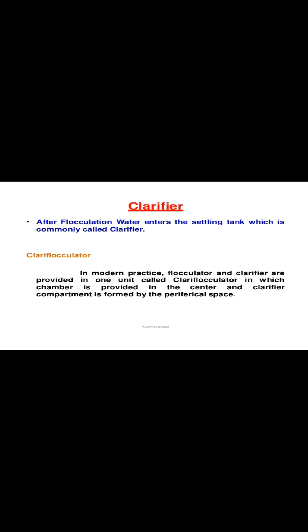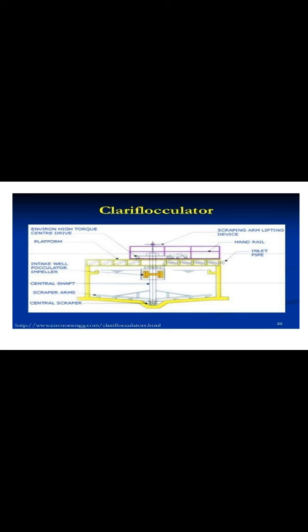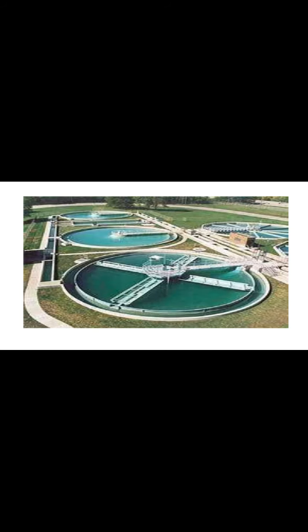Vertical baffle tanks are also used in flocculation tanks, where water flows vertically with baffle walls creating turbulence to facilitate mixing. After flocculation, water enters the settling tank — commonly called the clarifier. In modern practice, the flocculator and clarifier are combined into one unit called a clariflocculator, in which a flocculation chamber is provided in the center and the clarifier compartment is formed by the peripheral space.